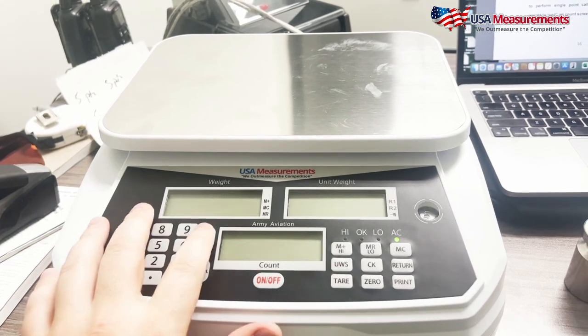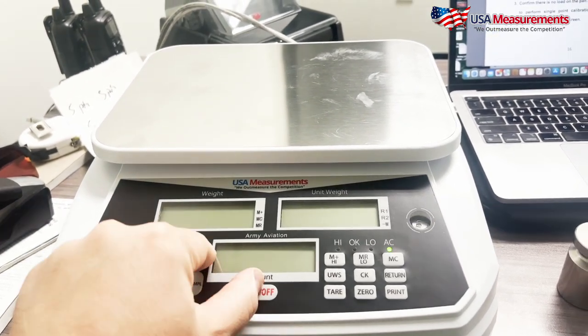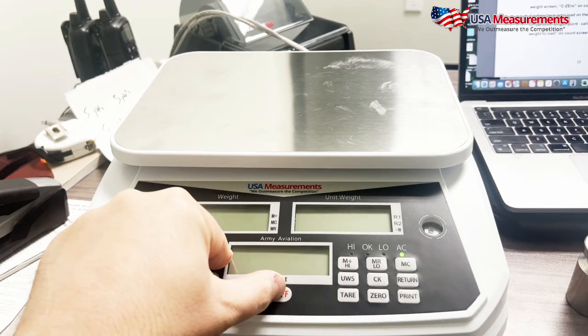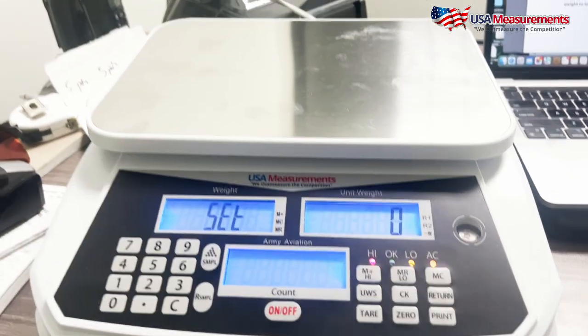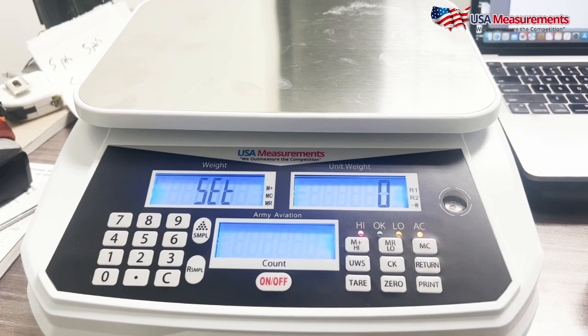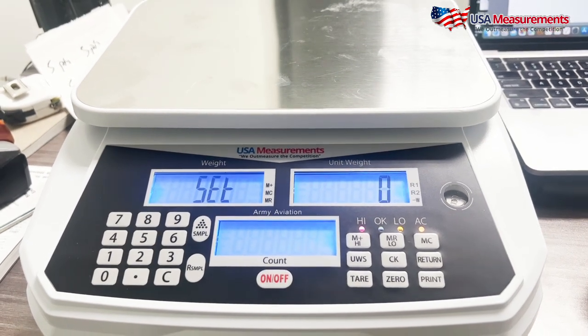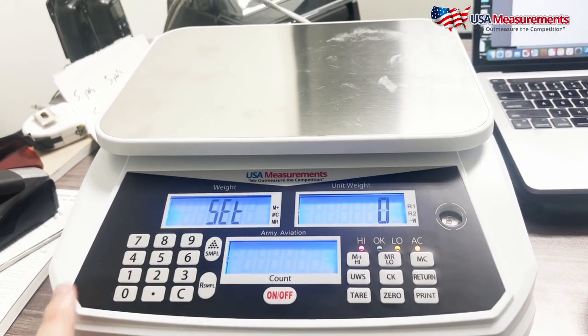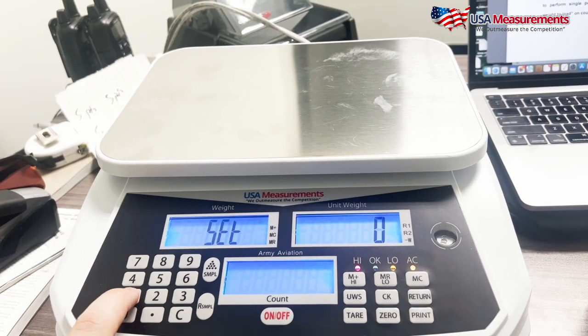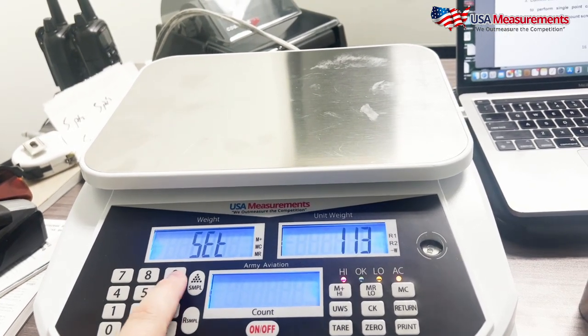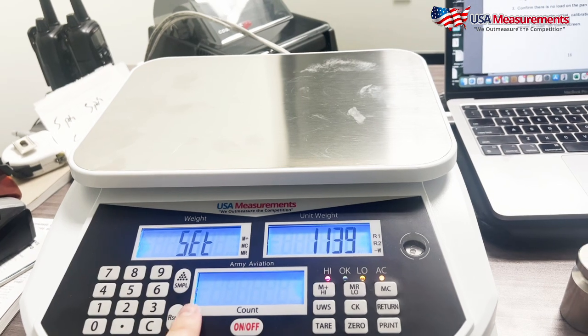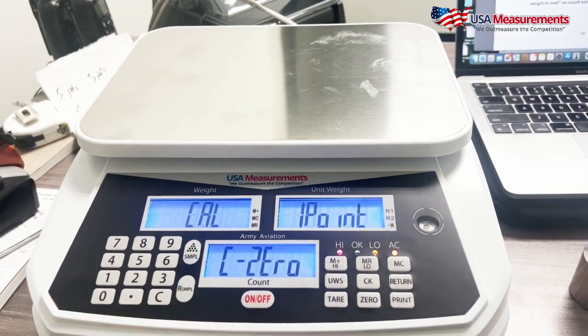Once the scale is powered off, you're going to want to hold the sample key here and then hit the on and off button at the same time. While you're still holding that button down, once you see set on the weight screen and 0, you can let go of those buttons. At this point, you're going to type in a PIN code. It'll be universal for everyone. 1139 will be that code. Once that's entered, go ahead and hit the sample key.